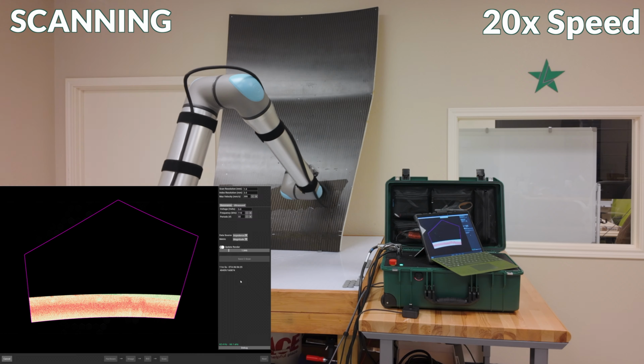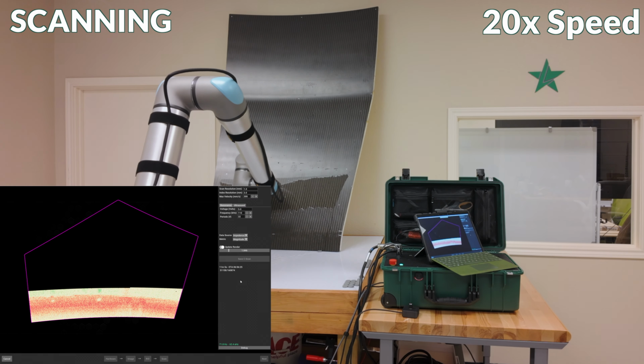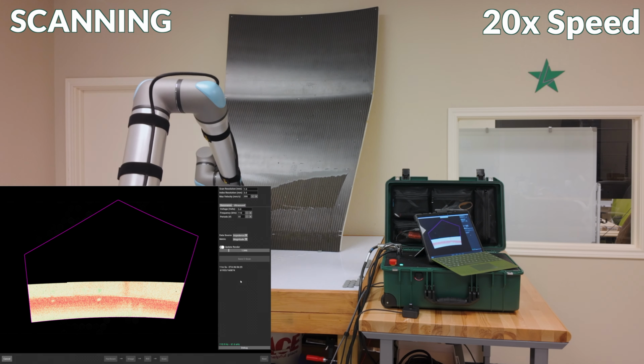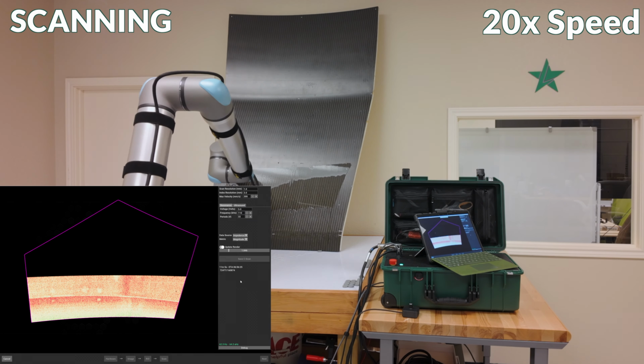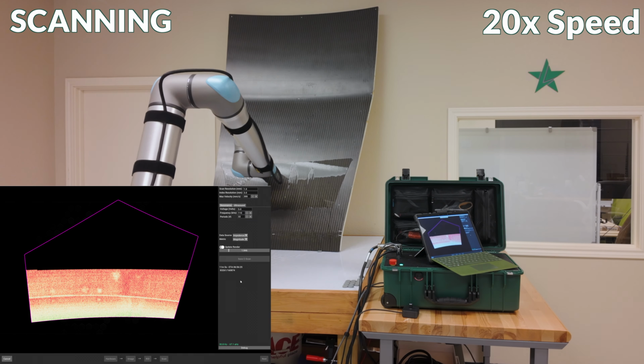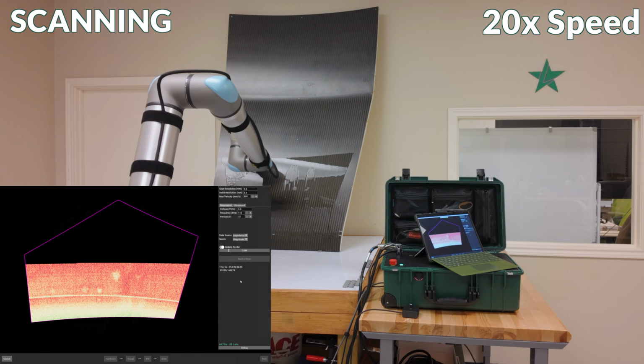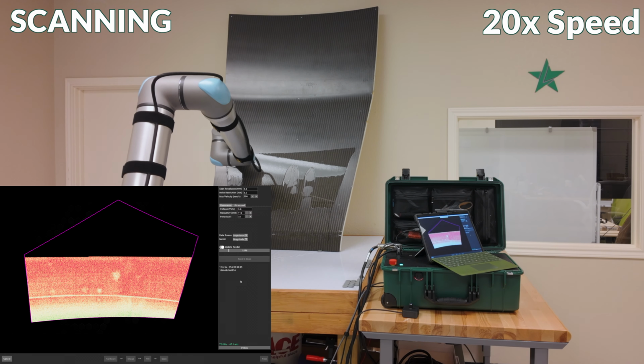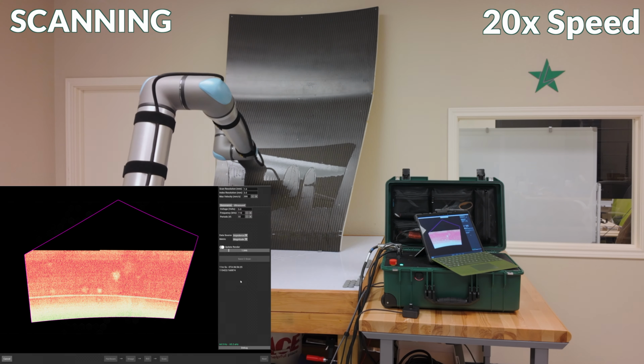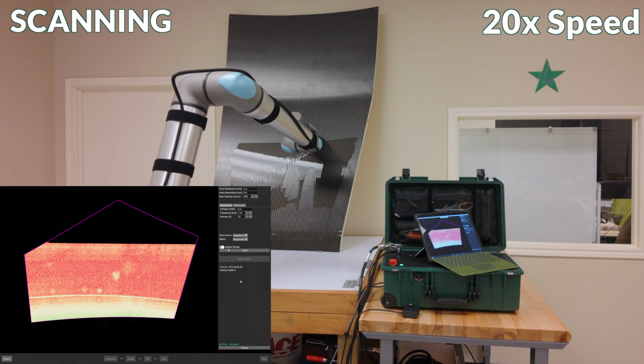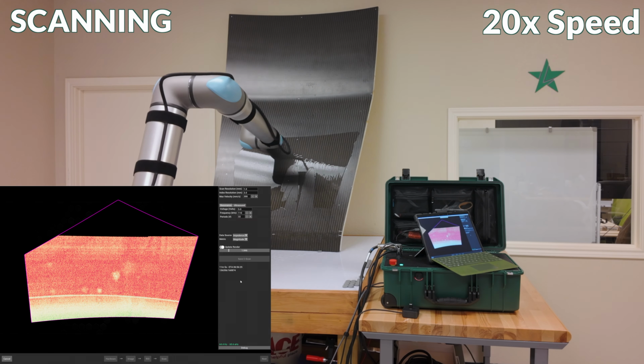After a few moments, the software will present a 3D wireframe of the scan region. Over the course of the inspection, the wireframe will fill in with C-scan data from the inspection. In order to ensure consistent coupling, the inspector is utilizing Lone Star's drip couplant delivery system. Drip pumps a small amount of water onto the part through the resonance probe end effector throughout the duration of the scan.